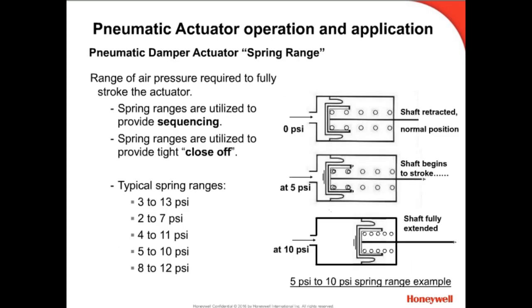The return springs in pneumatic actuators are available in spring ranges. A spring range is the air pressure required to begin the stroke through to the pressure required to complete the stroke. Spring ranges are available to complement a sequencing control scheme, or a particular spring range may be selected to provide adequate close-off pressure for a damper. In this example, the 5-10 psi spring will not begin to compress until 5 psi of air is applied to the diaphragm. From 5-10 psi, the shaft will move toward the fully extended position. Above 10 psi, the shaft remains extended. If this example was applied to a normally closed damper, the damper would be held closed with 5 pounds of spring pressure, which is the close-off pressure holding the damper closed.